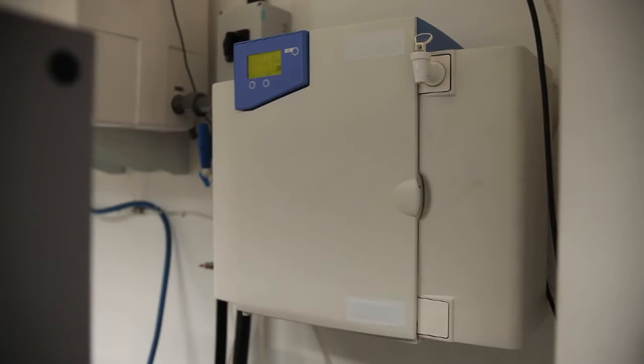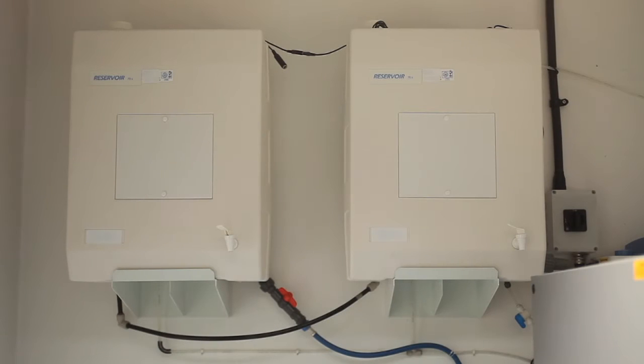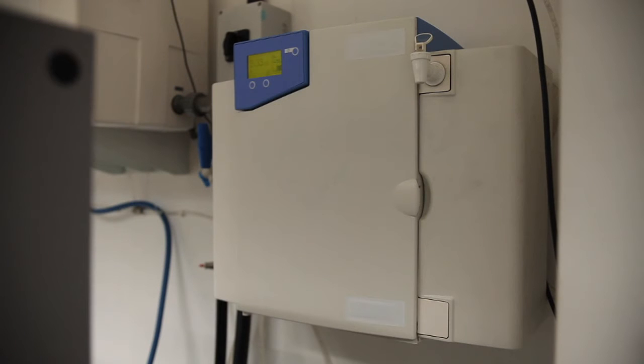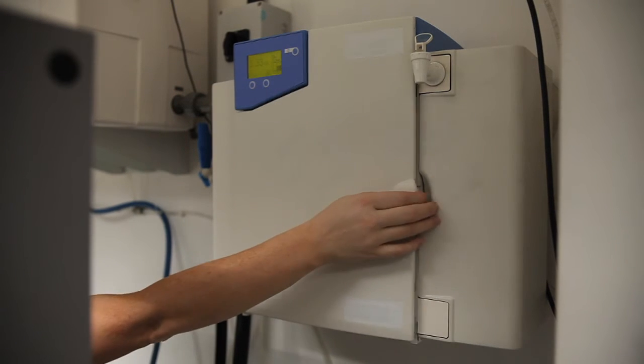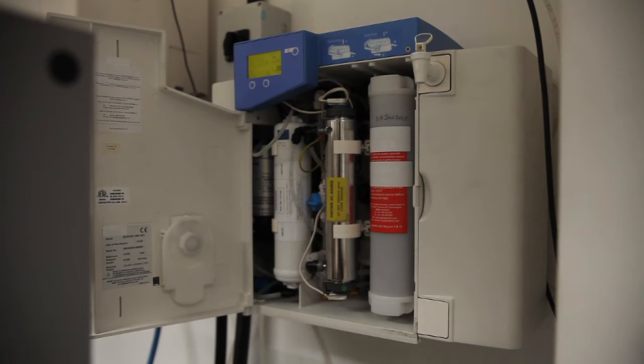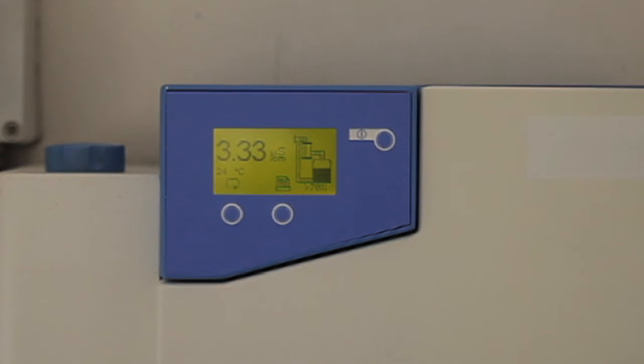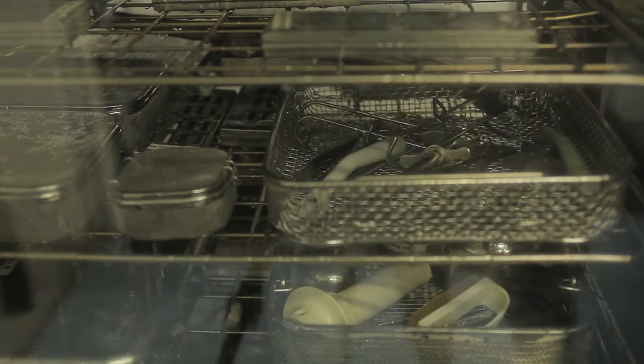Reverse osmosis water is recommended for the disinfection fill stage of the washer disinfector, as this water has very low levels of dissolved or suspended chemicals and minerals. RO water is usually generated on-site from a reverse osmosis unit. These units are usually equipped with a water reservoir for short-term storage of RO water. Such reservoirs are often equipped with an ultraviolet light treatment system to minimise microbial growth and multiplication. RO units used to provide RO water for autoclaves and washer disinfectors are normally configured to provide sufficient RO water for the daily demands of the equipment with minimal storage time. The quality of the water used at all stages in the cleaning process is critical to the successful outcome of the process, as the water is the last product to make contact with the RIMD prior to its subsequent use.